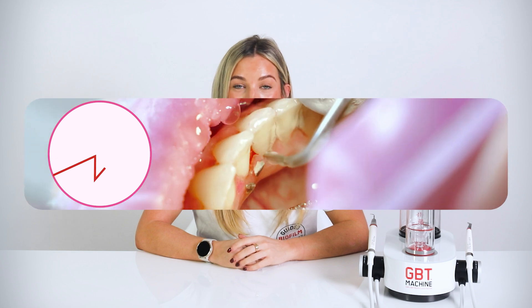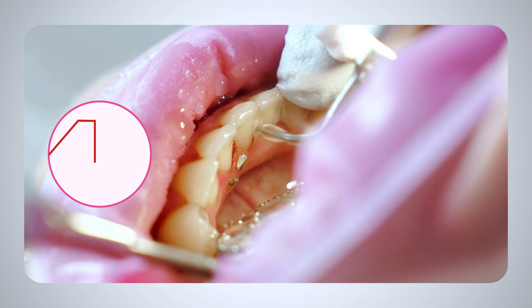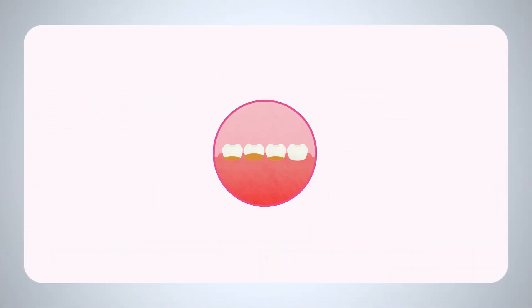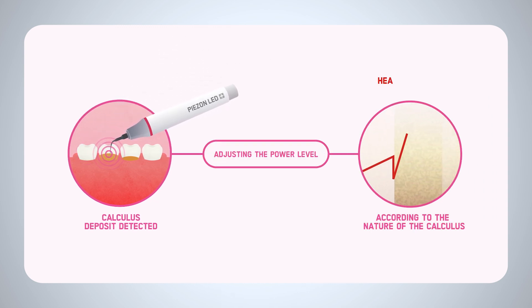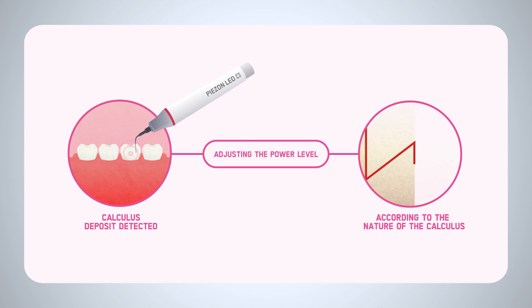The Piezon No Pain Max module adapts dynamically to the type of calculus encountered during treatment. It increases power for heavy deposits and reduces it for softer ones, ensuring a precise and tailored approach. Communicating with the PS instrument 125 times per second, the No Pain Max module provides real-time feedback, guaranteeing maximum efficiency. As the Piezon PS instrument detects the deposit, the module seamlessly adjusts power level progressively, increasing when necessary and reducing it once the calculus is removed.